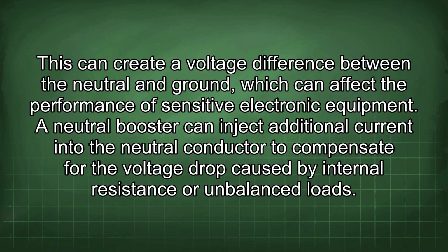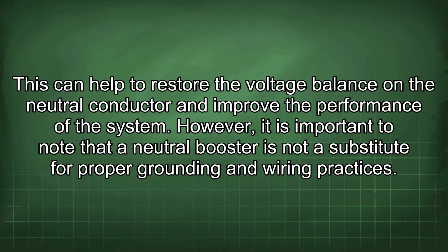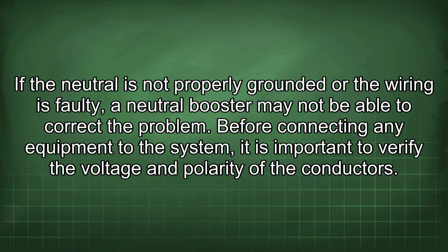A neutral booster can inject additional current into the neutral conductor to compensate for the voltage drop caused by internal resistance or unbalanced loads. This can help to restore the voltage balance on the neutral conductor and improve the performance of the system. However, it is important to note that a neutral booster is not a substitute for proper grounding and wiring practices. If the neutral is not properly grounded or the wiring is faulty, a neutral booster may not be able to correct the problem.